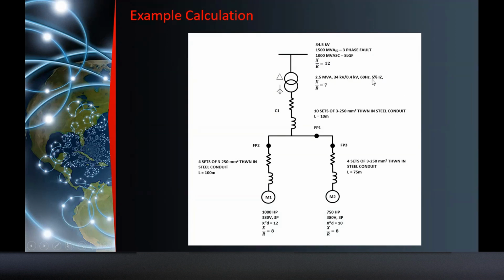Sir, what is the function of the 5% impedance aside from the short circuit you mentioned earlier? Didn't I mention earlier that you take the full load current of the secondary divided by the percent impedance? That is your fault current, 3-phase symmetrical at no load condition. So basically, for the 5%, take the 400 volts and multiply by 5%. So how much is that? 400 times 0.05, you will get 20 volts. Right? When you do a short circuit test on the transformer, 5% means 20 volts: you supply from the variac on the primary side and short the secondary.